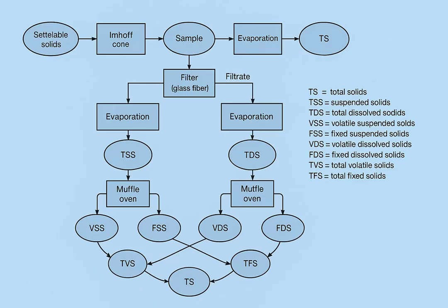Burns off. So that's mostly organic material. Generally, yes. It indicates things like microbes, plant fibers, grease, biodegradable stuff. What doesn't burn off is the total fixed solids, TFS. Which would be? Inorganic things like grit, salts, minerals, maybe some metals, things that don't combust at that temperature. So knowing the TVS, TFS split tells you about the organic load, potential for biological activity, things like that. Exactly. Or even potential for things like biogas production in some treatment processes.